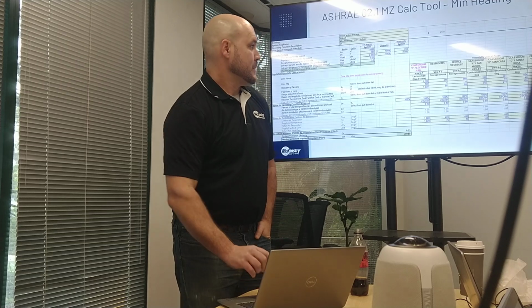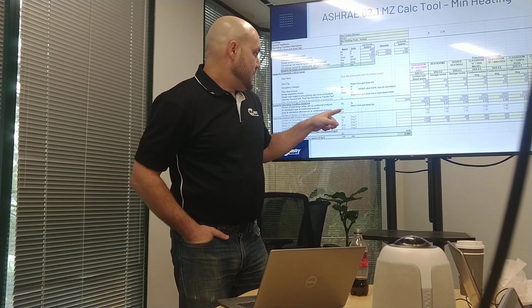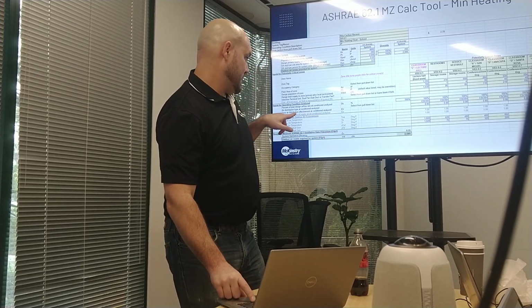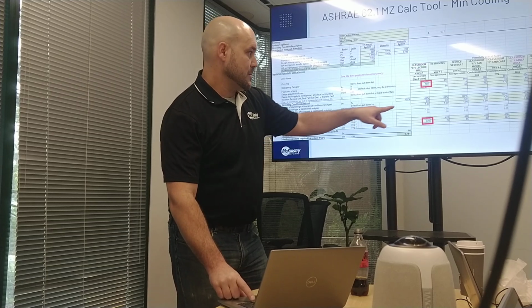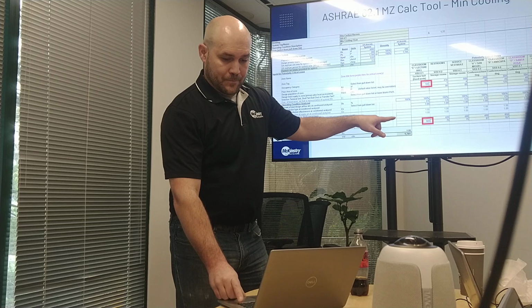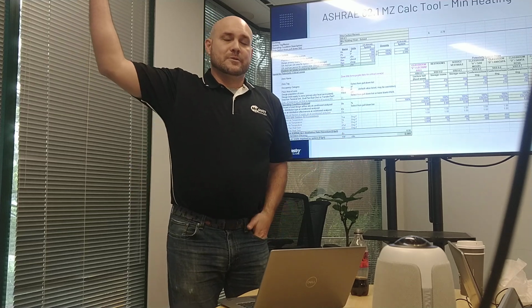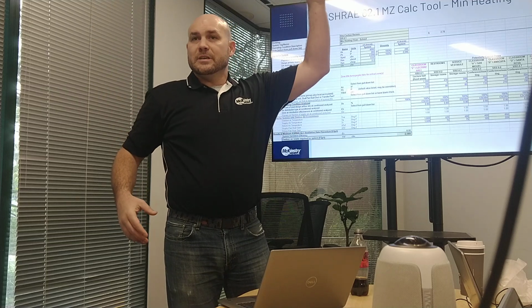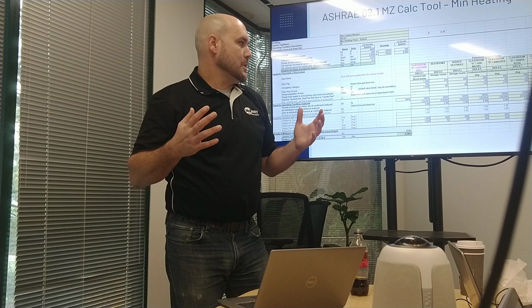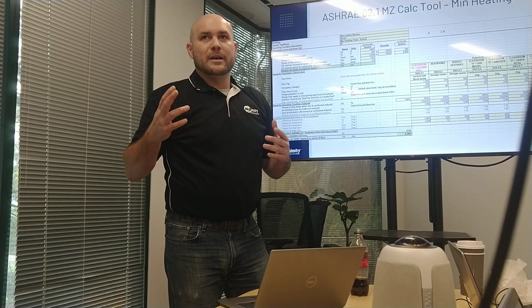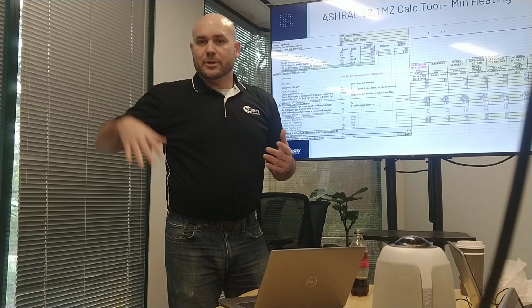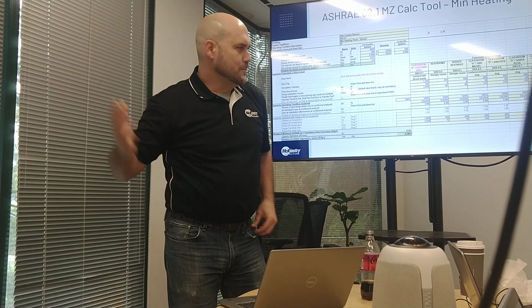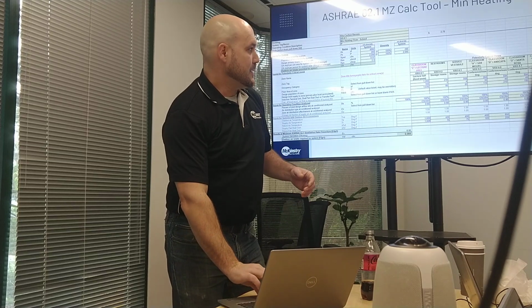In heating mode, what's different here is the ventilation effectiveness, because, let's go back to the cooling, it's 1 for cooling. In heating mode, it drops to 0.8 because in this particular space, the supply air is coming from the ceiling and it is returned at the ceiling, so Standard 62.1 says that only 80% of that fresh supply air is getting into what they call the breathing zone, which is below 6 feet in the space. What's curious is it doesn't matter whether it's a 10-foot ceiling or a 40-foot ceiling, it's still 0.8. But in any case, that dictates the effectiveness.